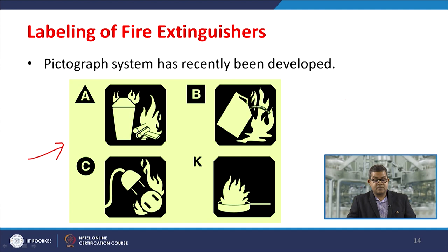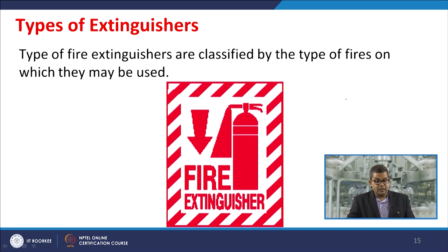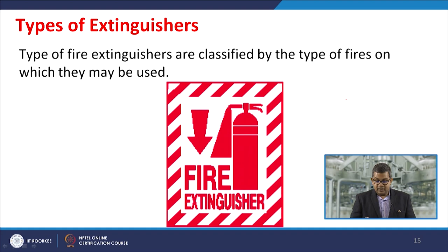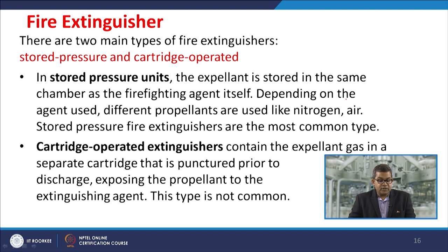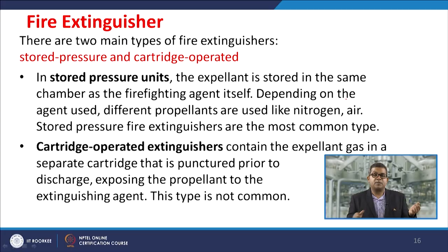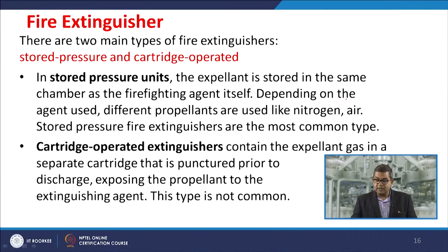Types of extinguishers are classified by the type of fires on which they may be used. There are two main types: stored pressure and cartridge operated. In a stored pressure unit, the expellant is stored in the same chamber as the firefighting agent, using propellants such as nitrogen or air. Stored pressure fire extinguishers are the most common type, found in domestic, office, and industrial settings. Cartridge operated extinguishers contain the expellant gas in a separate cartridge that is punctured prior to discharge, and are used for specific applications.